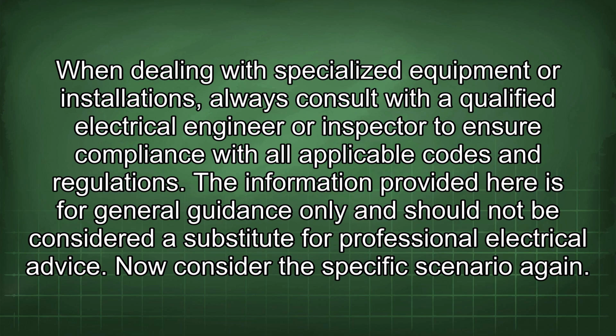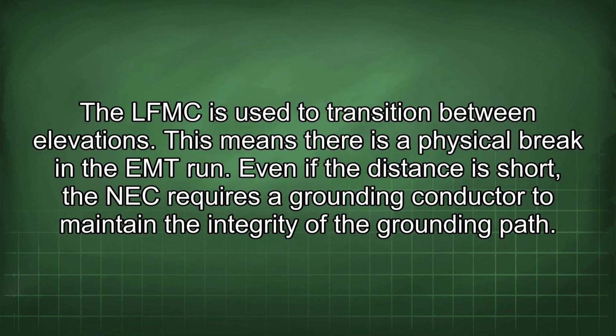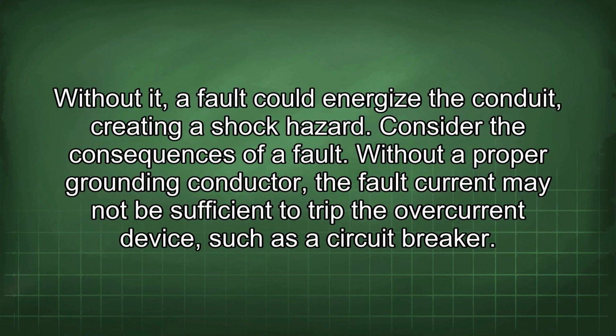Now consider the specific scenario again. The LFMC is used to transition between elevations. This means there is a physical break in the EMT run. Even if the distance is short, the NEC requires a grounding conductor to maintain the integrity of the grounding path. Without it, a fault could energize the conduit, creating a shock hazard.